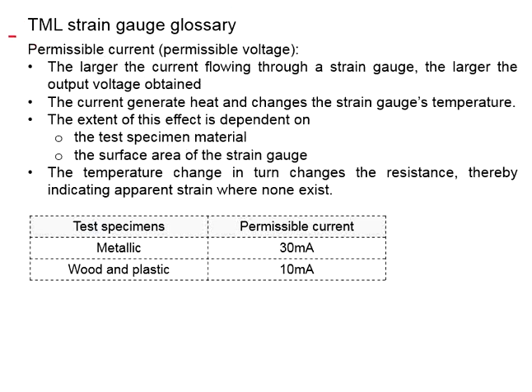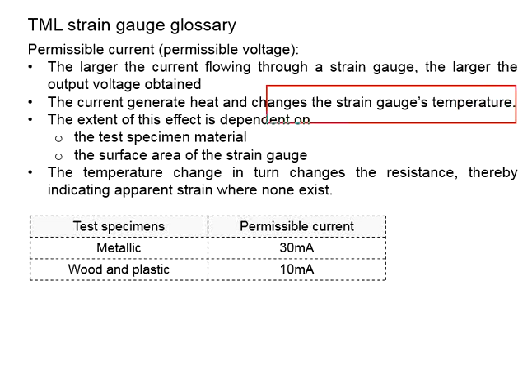Next, we talk about the permissible current, or we can say it is related to permissible voltage. The principle is this: the larger the current flow through a strain gauge, the larger the output voltage obtained. However, the current generates heat, which changes the temperature of the strain gauge. You know that strain gauge is susceptible to temperature, and temperature can lead to inaccurate measurement.